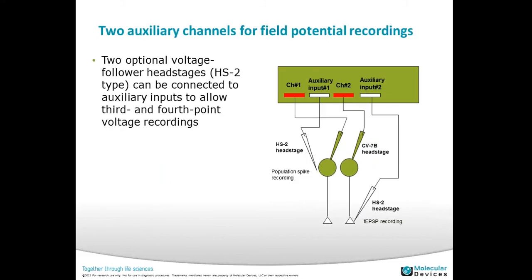On top of that, a few customers noticed that you also have two auxiliary channels that allow you to record two additional field potential recordings. At the back of the 700B, you'll see two inputs, called auxiliary input one and input two. These two channels you can connect to another two head stages, but not CV7B, it's HS type.